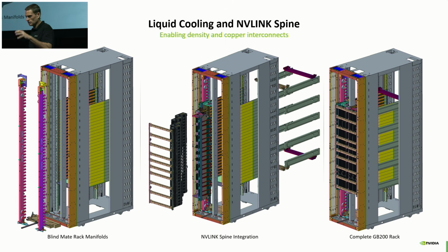Forever—it's spring-loaded, and for the entire service life, the rack has to support that weight. If you put that into an off-the-shelf rack, it would simply bow and nothing would work. So we created all of this mechanical structure, did a lot of iterative design and simulation, and came up with a structure stiff enough to only deflect tenths of a millimeter under that load. You can see those braces coming out the right-hand side of the rack.